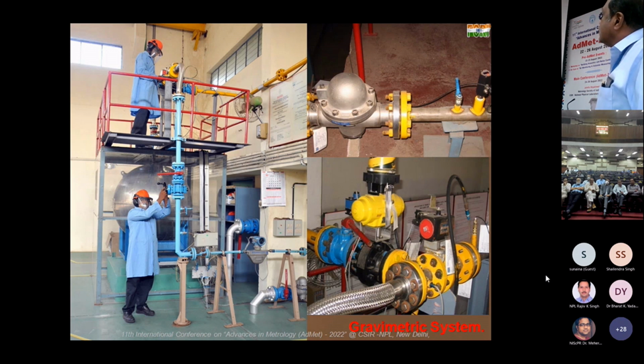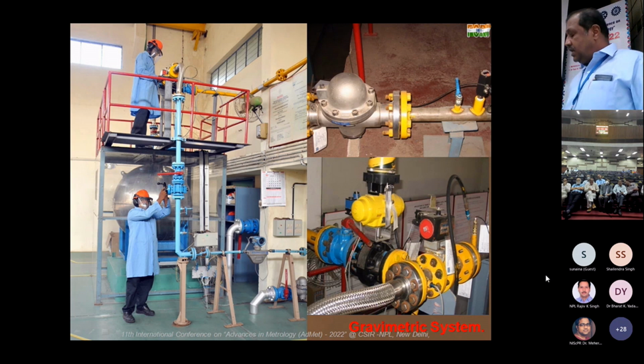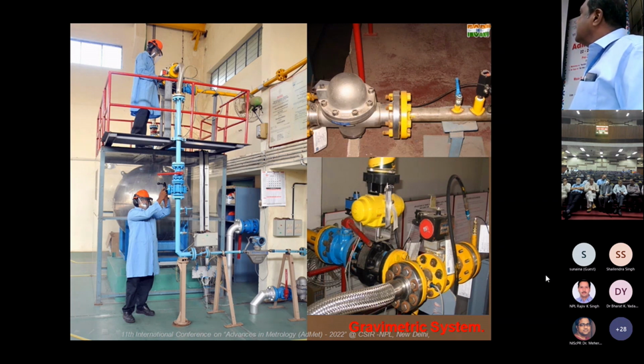Initially we divert to atmospheric pressure. This is the photograph of that system. Since the balance is very sensitive, we put a perspex enclosure so that local air movement does not affect the mass measurement. Initially we were using it for calibration of thermal mass flow meters, and now we are restricted to using the system for the calibration of our reference system only.